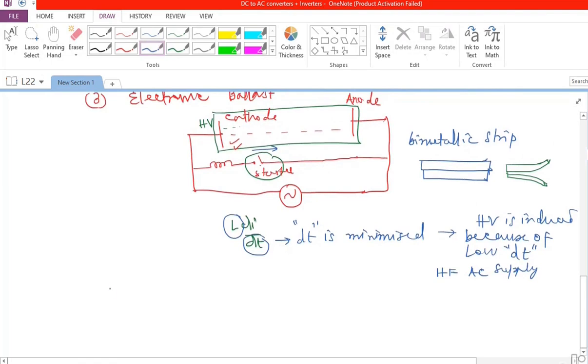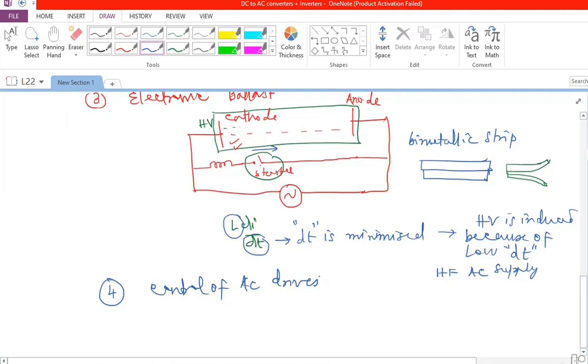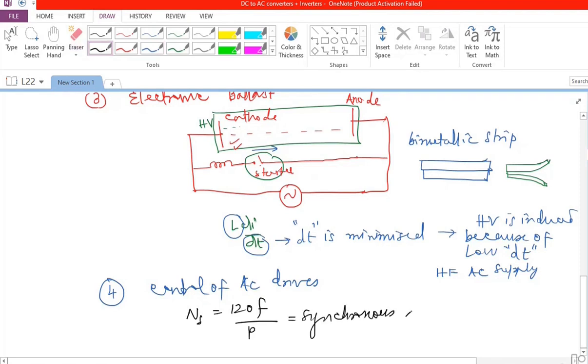One more major application of inverters is the control of AC drives. For a synchronous motor or induction motor, applying a variable frequency voltage changes the speed, since synchronous speed is 120F/P. By changing frequency with the help of an inverter, the speed of the AC motor can be controlled. All industrial drives nowadays are fed by inverters — typically three-phase inverters for three-phase induction or synchronous motors.